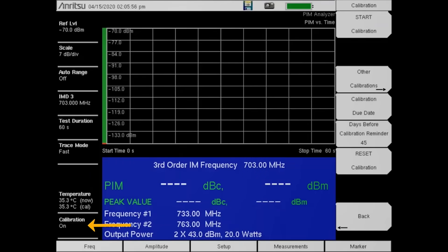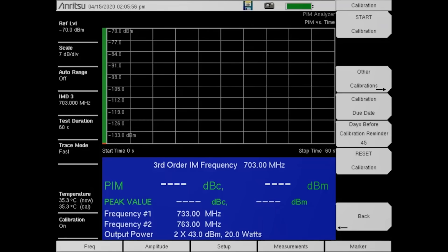Once the calibration is complete, we will save the setup file. Because calibrations are saved with the setup, saving the setup allows for the setup parameters to be retrieved with the calibration.